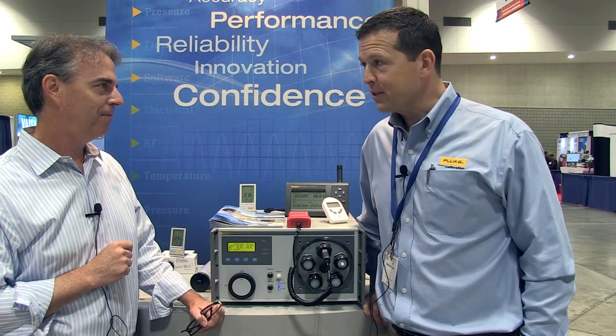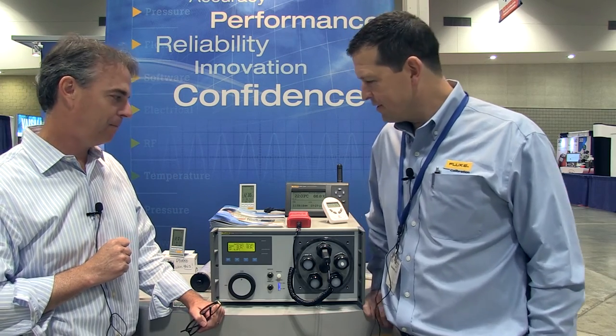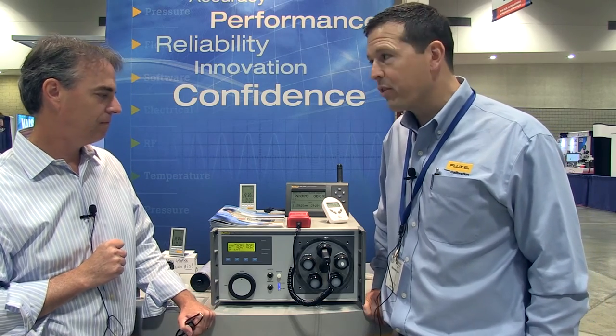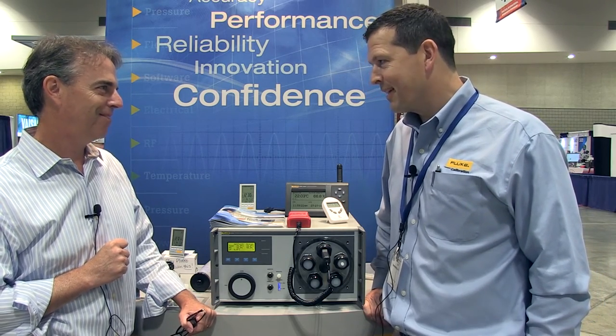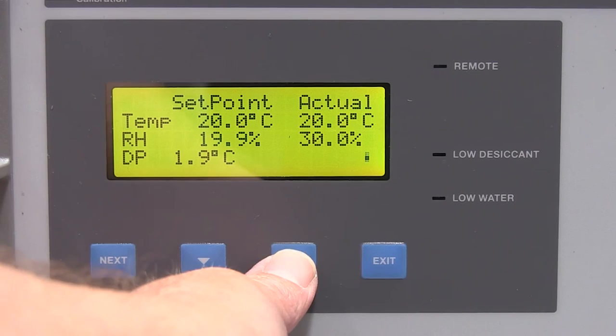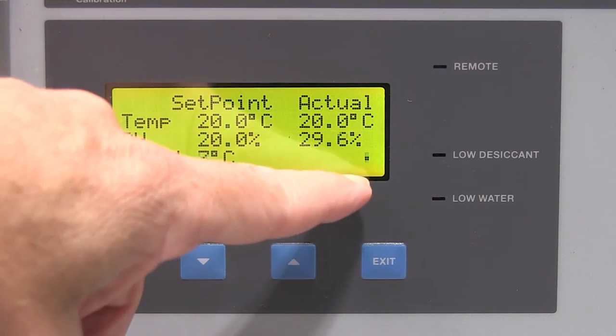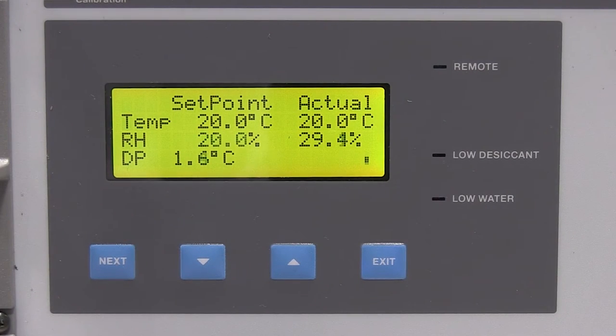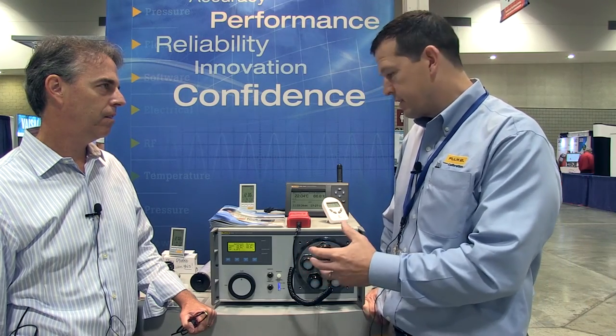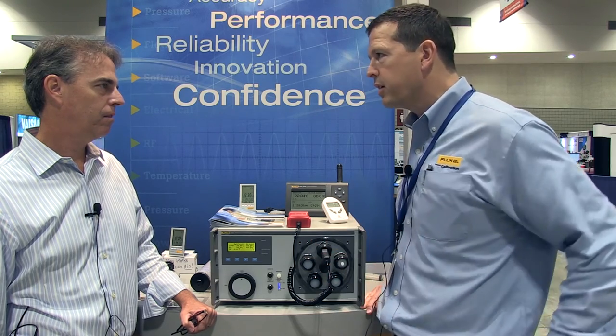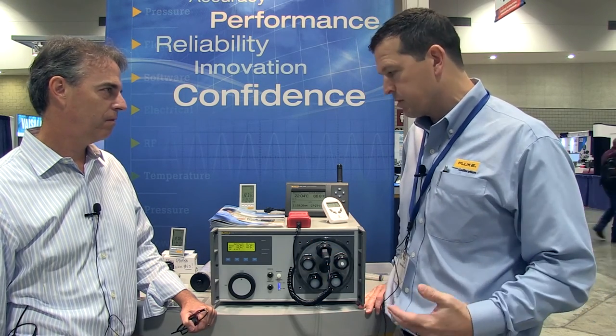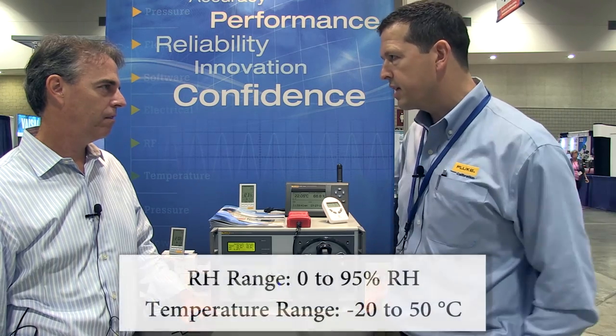It's our first humidity calibrator ever, called the 5128 - we call it the Rapid Cal. As the name suggests, it's built for speed. It's a mixing flow humidity generator, meaning it takes a wet stream of gas coming from a humidifier and a dry stream of gas coming through a desiccant, mixes them together, and quickly generates humidity so you can do calibrations. It also controls temperature up to 50 degrees C, so you can do humidity and temperature points.